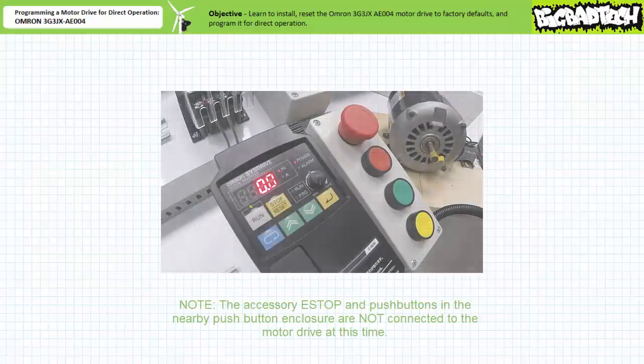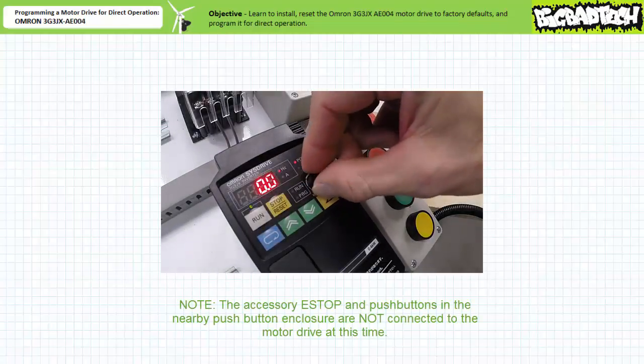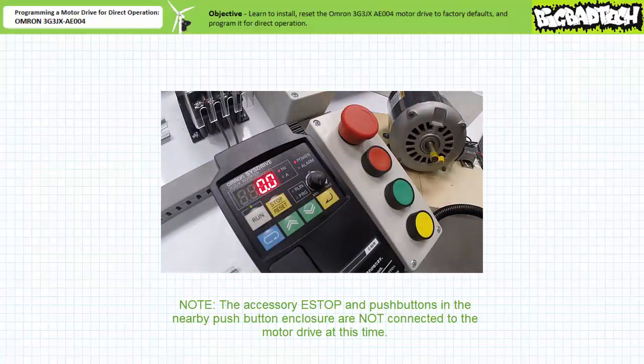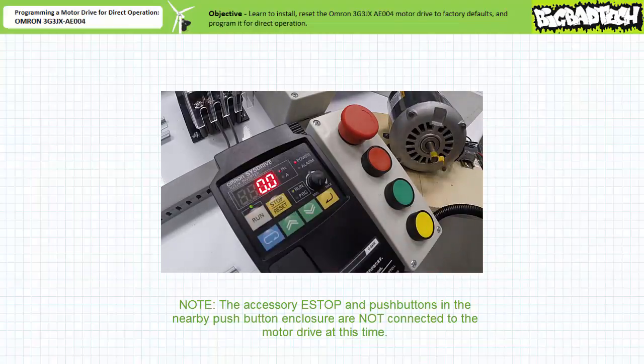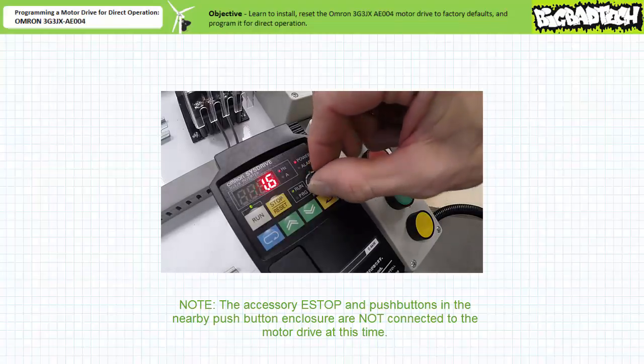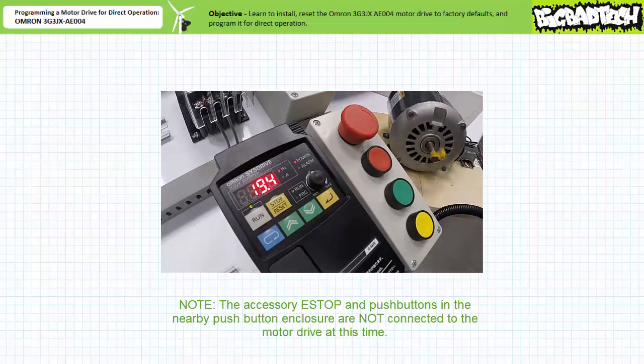We'll operate this motor with parameter D001, the output frequency monitor being displayed. To directly operate this motor, an operator would position the frequency adjustment knob all the way counterclockwise, corresponding to minimum excitation frequency, and press run. Note the run LED indicates the motor is in operation, but it's not moving. As an operator repositions the frequency adjustment knob clockwise, the motor drive increases applied frequency.